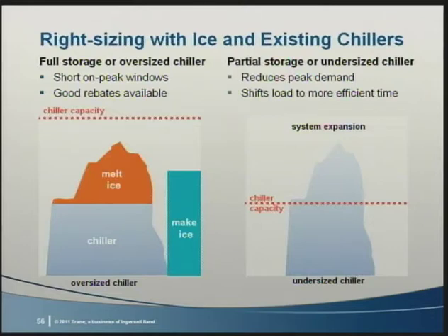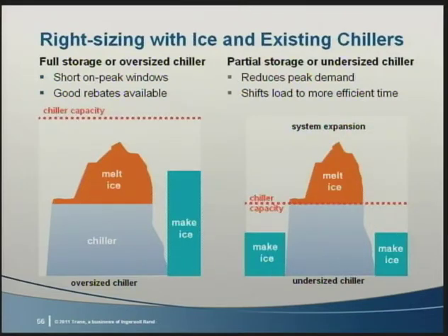Conversely, if your building has too small of a chiller, instead of adding more chillers, ice can be your system expansion. Here we have a fully utilized chiller doing all it can on the design day, and ice made when the loads are reduced makes up the difference. You may recall we discussed ice storage design and control in a 2009 broadcast. Chiller capacity reduction due to glycol must be considered when defining the operating modes.